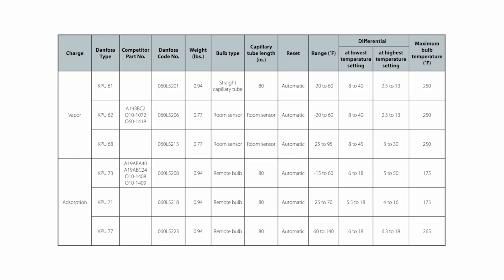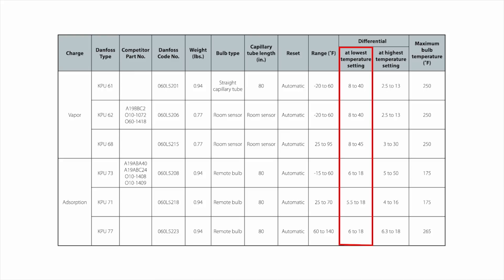I want to come back to the differential and how it is affected by evaporator temperature. A thermostat will have either a fixed differential or a differential range you can adjust. The caveat is that value is specified at a specific evaporator or space temperature. If you deviate from that temperature the differential is going to either increase or decrease — the lower the evaporator or space temperature, the larger that differential is going to be.